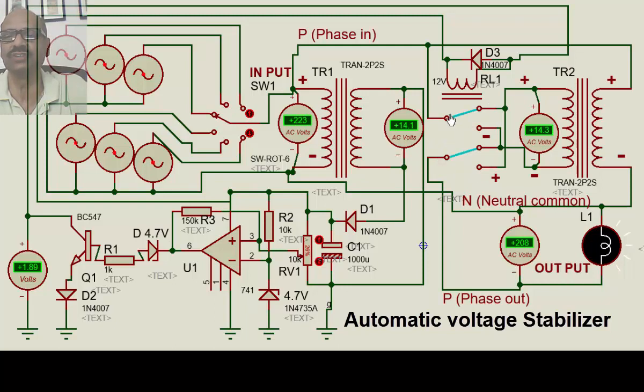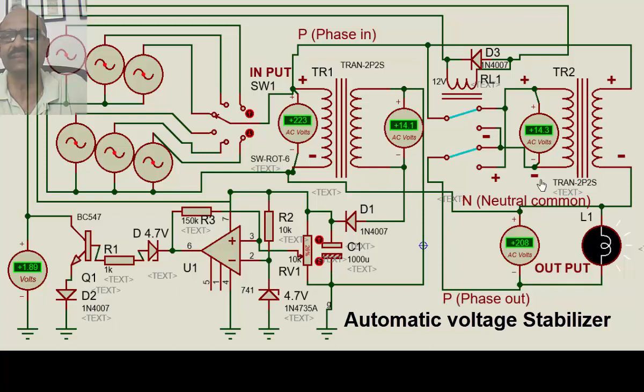When the input reaches a certain level, the relay changes from this position to this position. Now positive goes to positive — meaning the secondary voltage is subtracted. 223 V minus 14.3 V gives about 208 V. This is how the buck operation takes place.